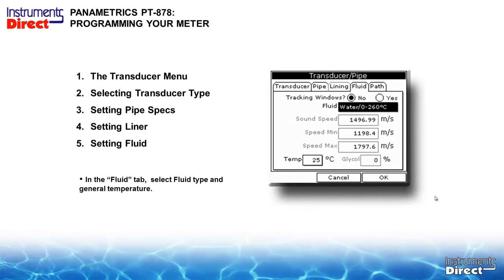Now we select the liquid, so we go to the fluid tab. It's a drop-down menu of all the different process liquids. It will automatically default the sound speed for you. If you have a unique temperature situation, there's a place to plug in the temperature on the lower corner of the display itself. For the most part, the device here is probably plus or minus 10% of the sound speed, and you're really not going to have any significant differences.